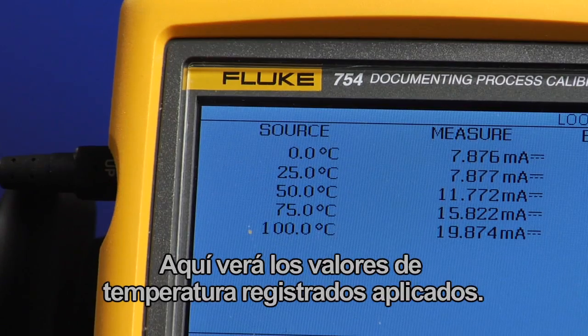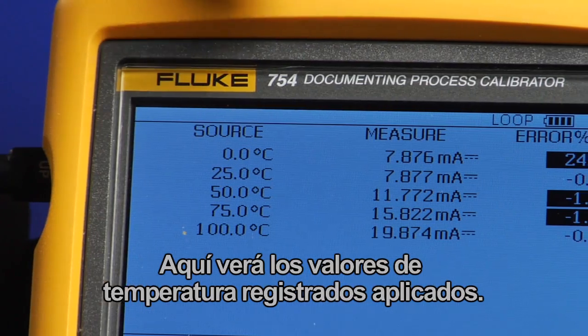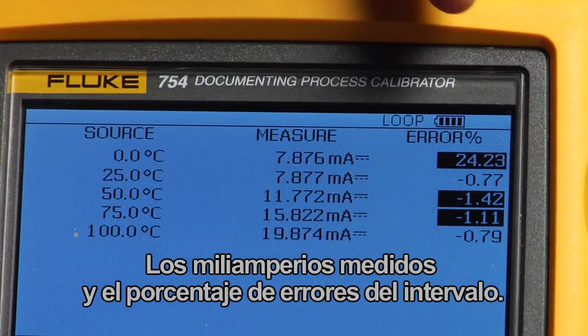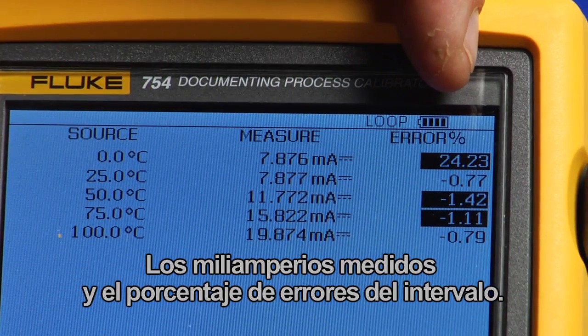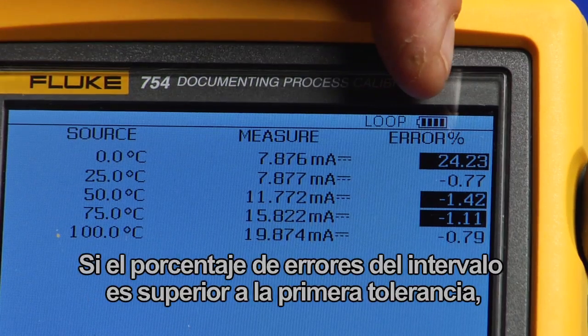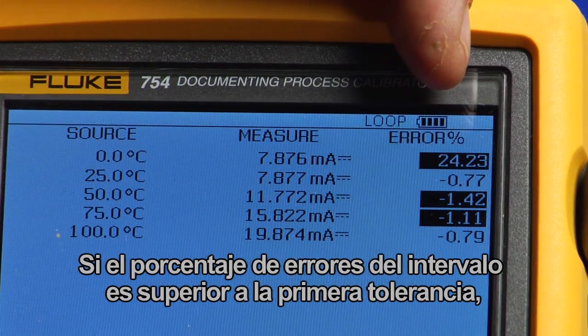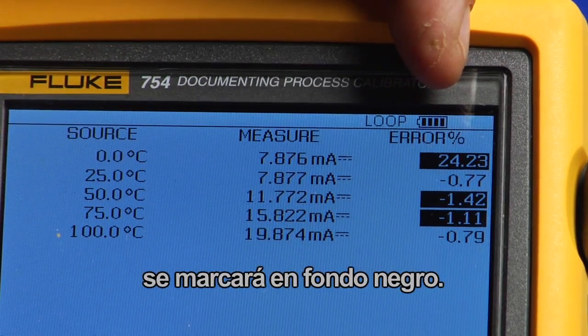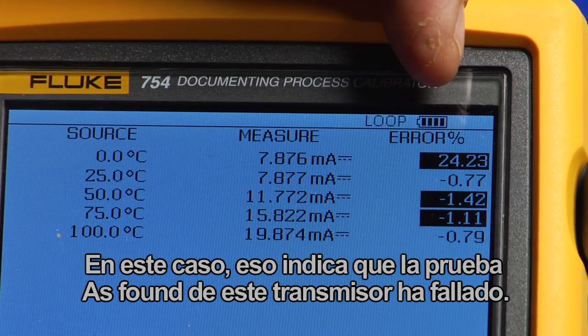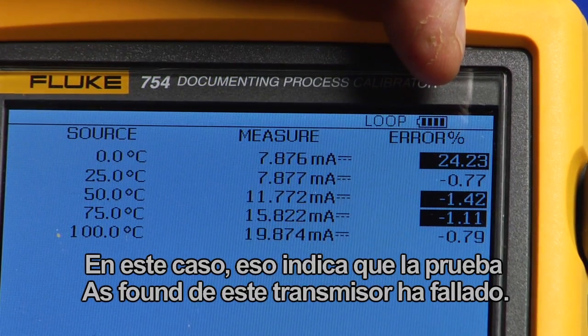Here you see the recorded temperature values that were applied, milliamp values that were measured, and the errors as a percent of span. If the error percent of span is greater than the test tolerance, it is flagged in reverse video. In this case, this indicates that the as-found test of this transmitter has failed.